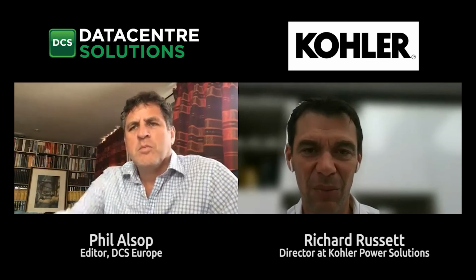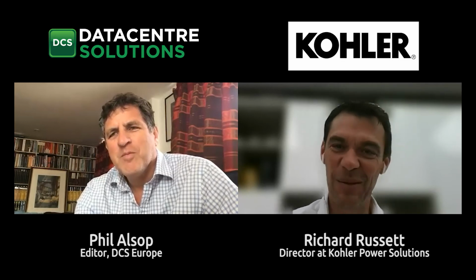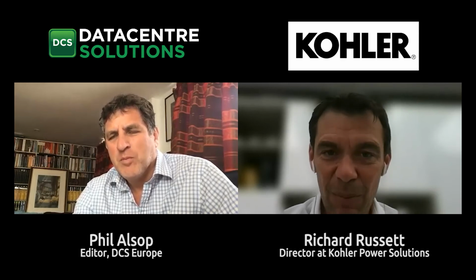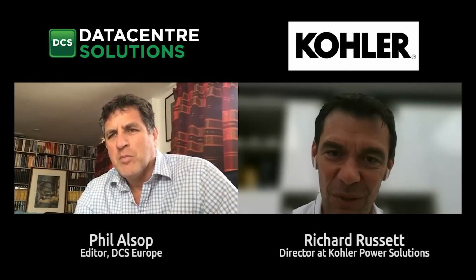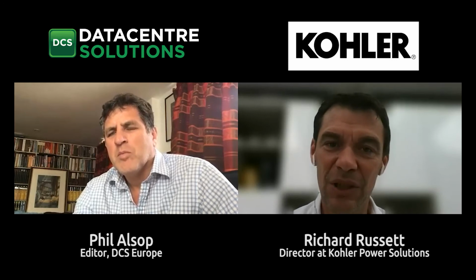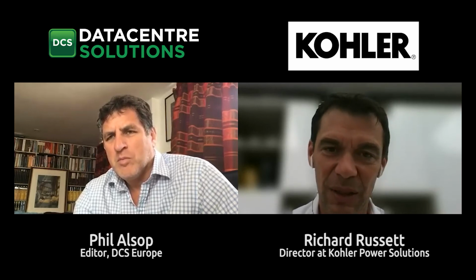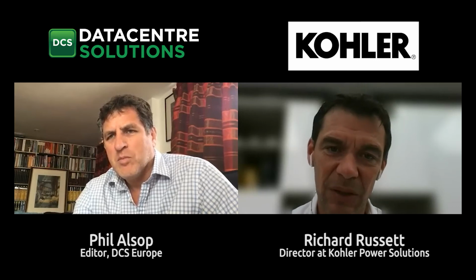I mean, London being a good example, if you go to certain parts of London, there are enormous numbers of diesel gensets, whether they be ours or anybody else's. So an instability in the grid or a network outage in those parts of metropolitan areas would have an impact, because you're going to have a lot of equipment starting. And some of those have been built for 10, 15, 20 years, so they don't have the same level of technology or the same level of emissions treatment as what's possible today. So I think it will come under more scrutiny, and there will be a requirement to fit the best available technology, which may not have been expected in the past.